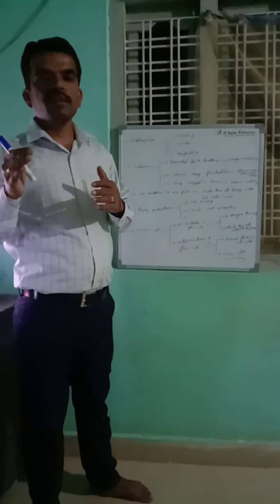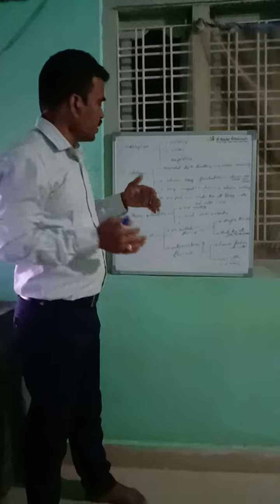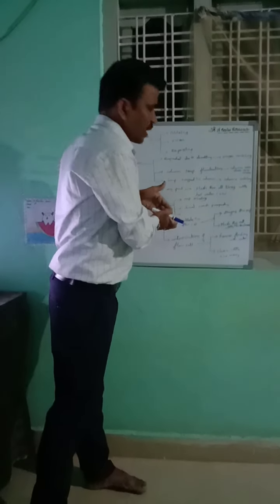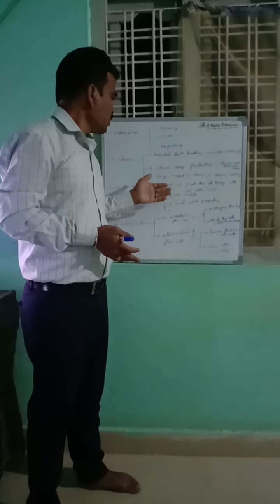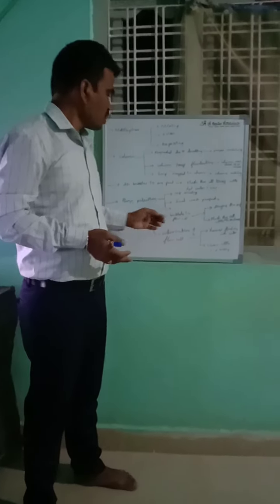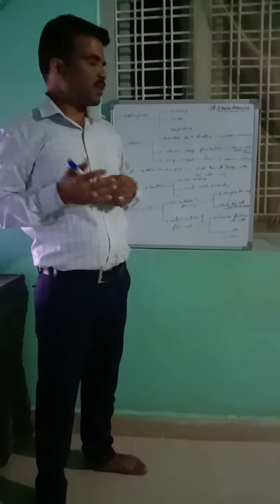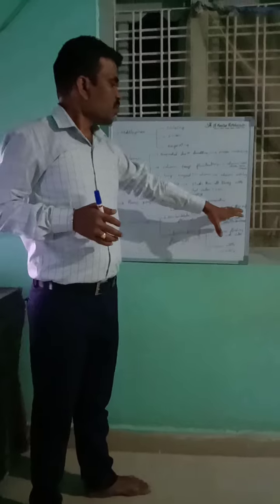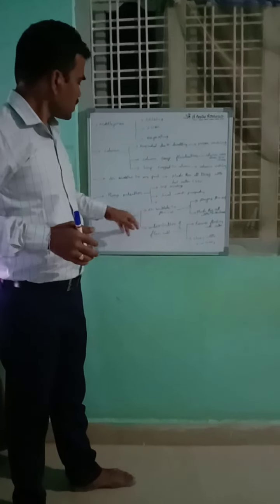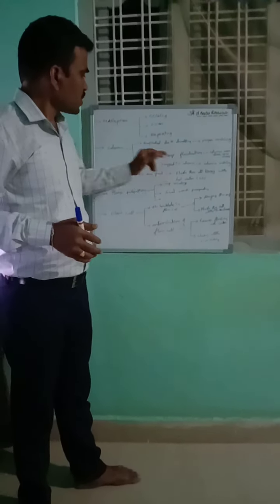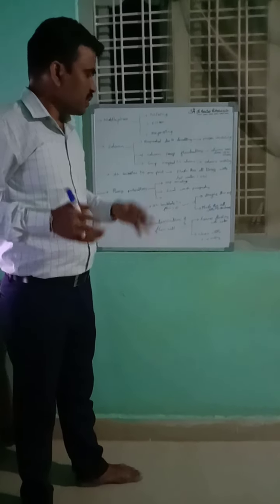If you have not done the mobile phase degassing, you may get air bubble trapping in the flow cell, flow lines, all ports and this flow cell. Due to that we will get some abnormality. So we have to degas the mobile phase properly, then we can prevent air bubbles being trapped in the flow cell and also all ports of the lines.